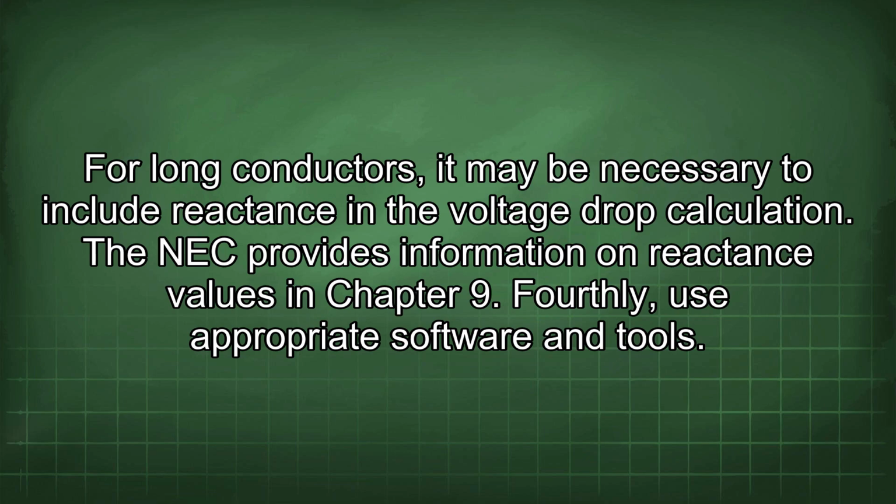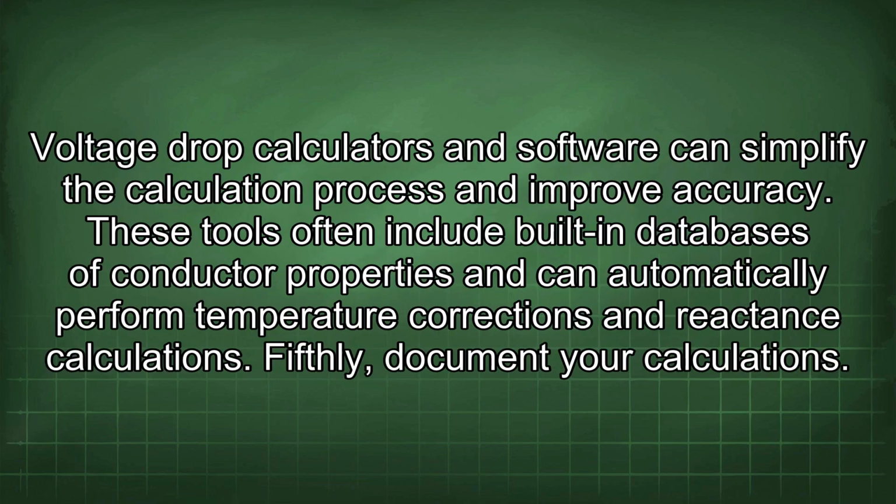Fourthly, use appropriate software and tools. Voltage drop calculators and software can simplify the calculation process and improve accuracy. These tools often include built-in databases of conductor properties and can automatically perform temperature corrections and reactance calculations.